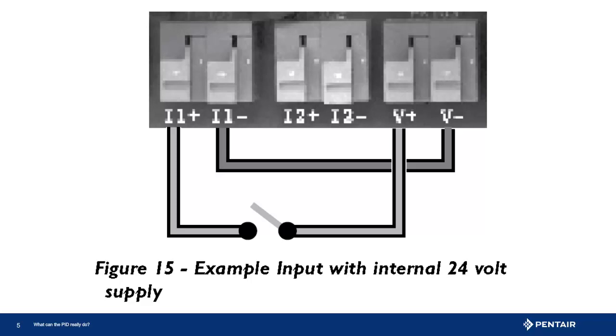Here we see a simple 24 volt connection to an input. Following the flow, the control we wish to use is connected to V+. Going right to left, the voltage travels down the wire to the control shown open here. When the control closes, the voltage flows to the input, in this case input 1 plus side. Now to complete the circuit, a wire or jumper is connected to input 1 negative. The other end of the jumper wire is connected to V negative and completes the circuit.